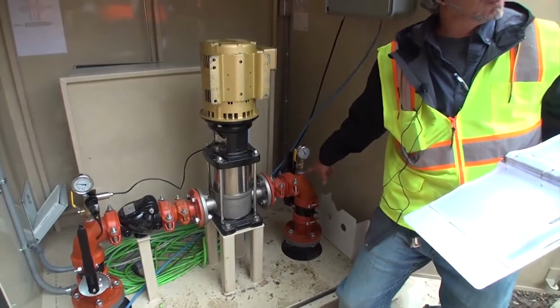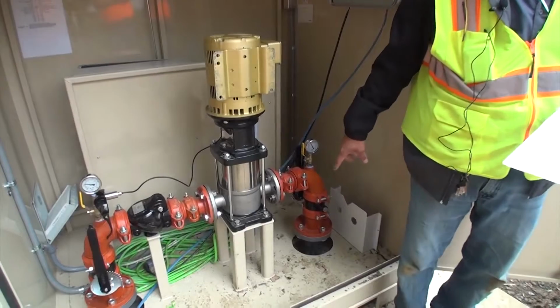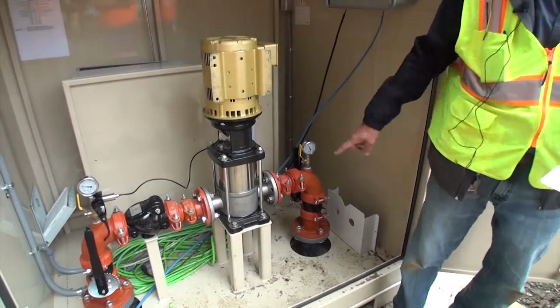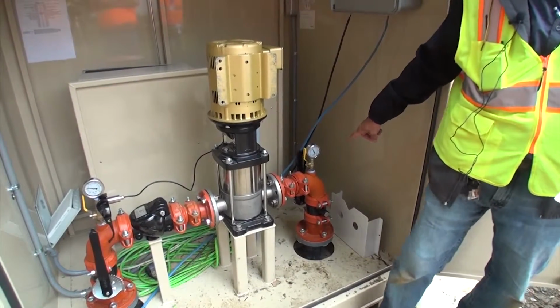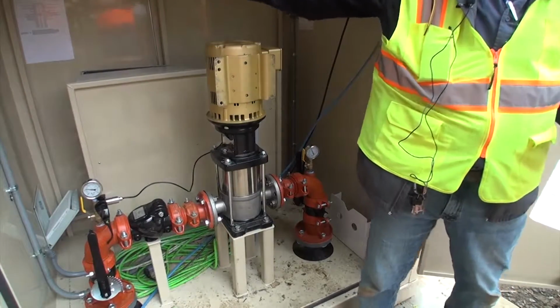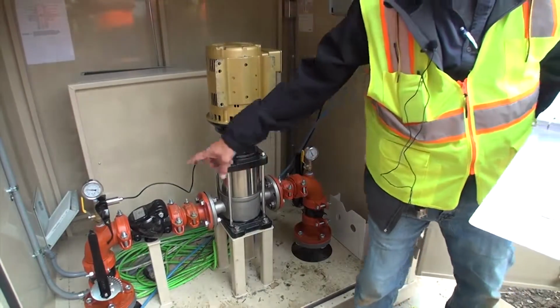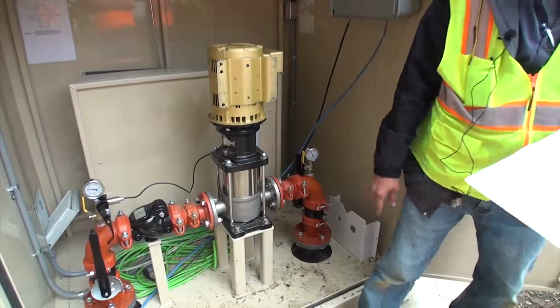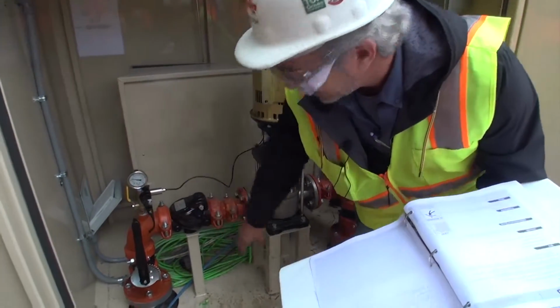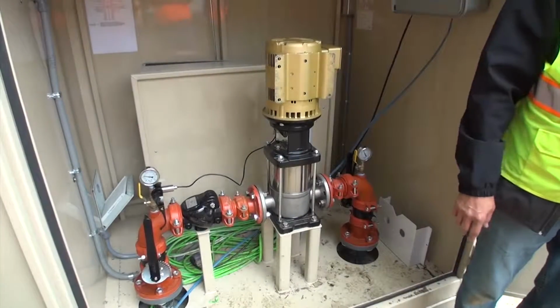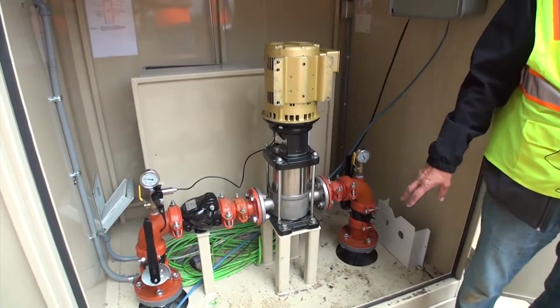Probably the first thing you want to do is pull this out here and put your air compressor on there. Blow out all your lines. If you blow it from here on your suction side and blow it all the way out, you're going to be clearing all of this and you're going to be okay. Otherwise, you're going to need to pull these clamps and drain the water out of that check valve and drain the water out of the pump so they don't break.